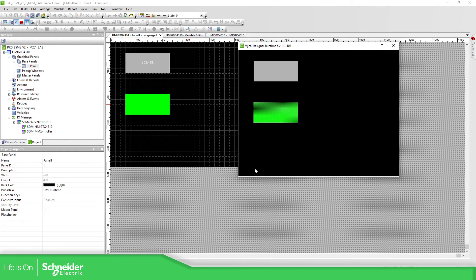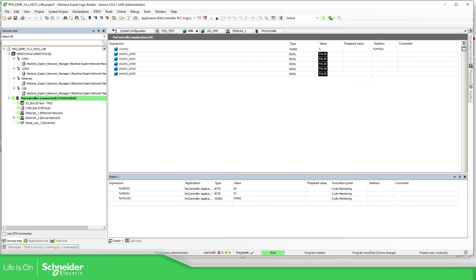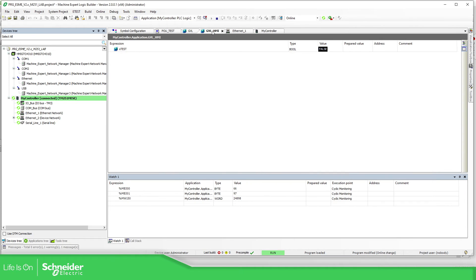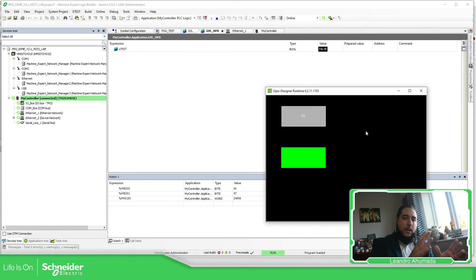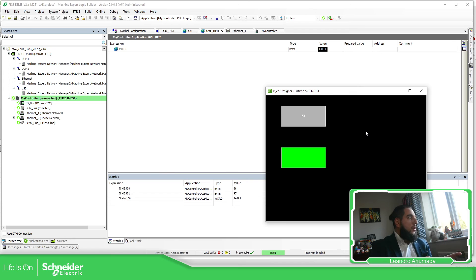Now if I simulate this again, we should be able to communicate with the PLC without any problems. Let's wait for this to finish. There we go. If I change this to 51, and go to the HMI part, we should be able to toggle this. So what we have done is shown how to communicate the PLC in Machine Expert with the HMI in Vijeo Designer. Use a symbol configuration to share all the values you want with the HMI. Once you've added the values on the HMI, define the node name on the PLC side. Once the node name is defined, check the security. Once security is checked, download to the target and you should have communication.